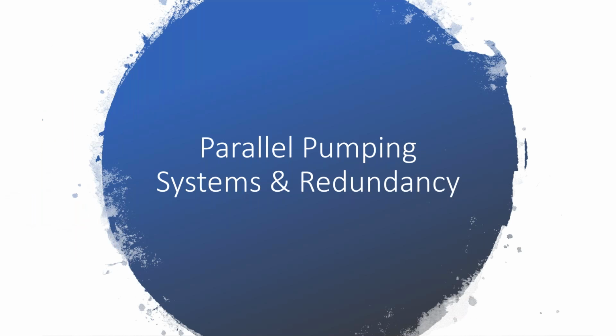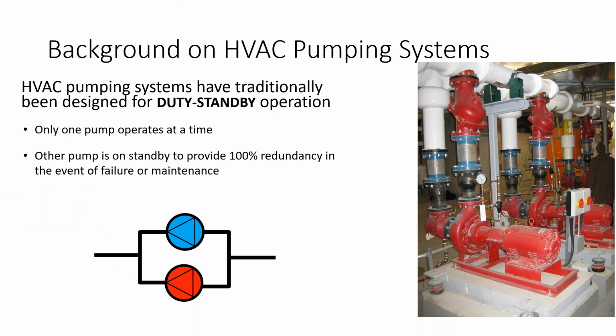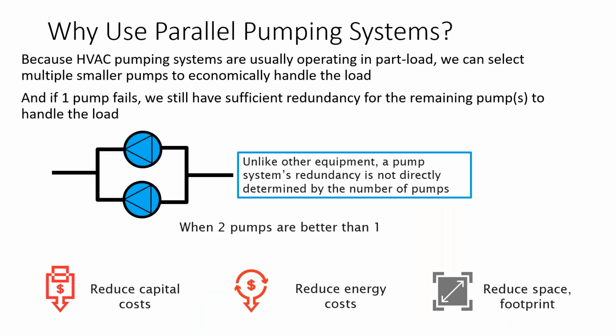So now we integrate parallel pumping systems and redundancy. The background on HVAC pumping is basically we would have one pump operating at a time, and we have a standby pump at 100% flow in redundancy in the event of failure or maintenance. So we'd have the swing lever and we'd just crank up the second pump. What we found is that that's not exactly the best way to go about it when we're dealing with our carbon footprint issues, and I'll show you why.